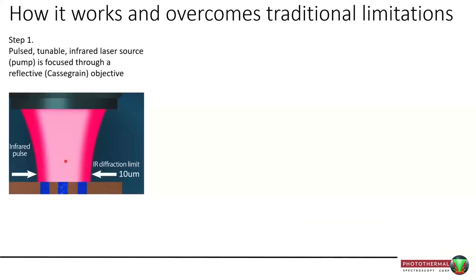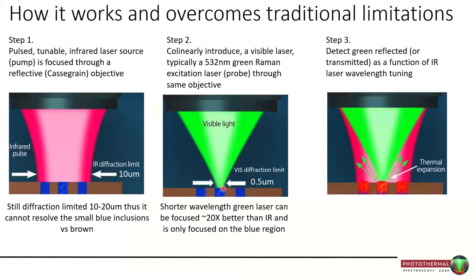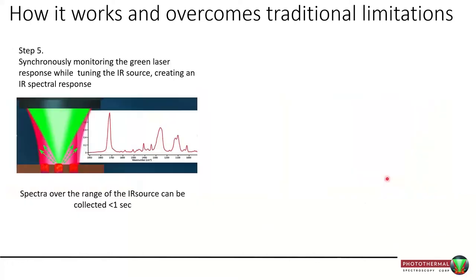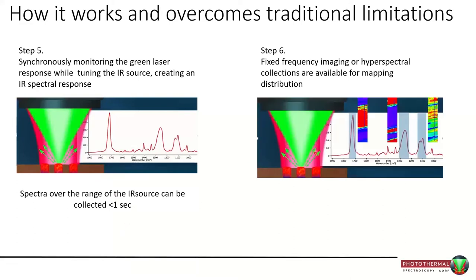How does it work? We deliver pulsed infrared light through a regular Cassegrain objective onto the sample surface, which has a fairly wide diffraction limit. At the same time we deliver the visible probe beam, focused to a much tighter spot. As we tune our infrared wavelengths, absorption at certain points generates thermal expansion and changes in refractive index. These together change how the green light is reflected back, so we measure green light intensity as we tune infrared wavelength and extract the infrared spectrum. Using the QCL, you can also do fixed-frequency imaging.